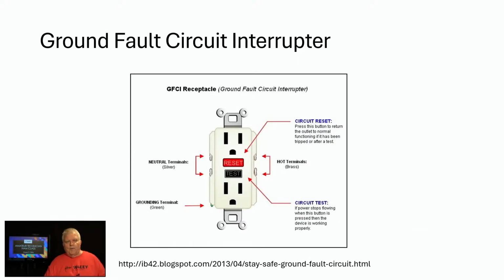Ground fault circuit interrupters are now required by electrical codes locally, in areas where there might be a life hazard issue if you were inadvertently part of an electrical circuit. We're talking kitchens, bathrooms, outdoors, garages, things like that. It's an additional safety system that measures the current flowing from the black hot wire, on the narrow prong on top, going to the load, and then measures the current coming back on the white wire, wanting them to be equal.